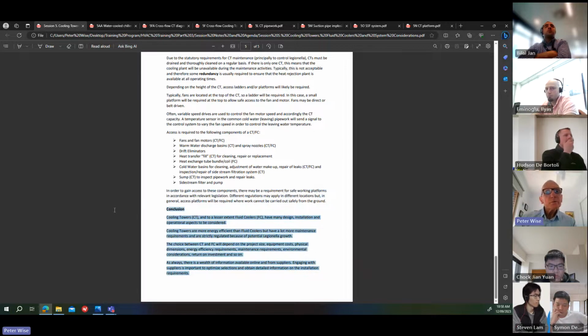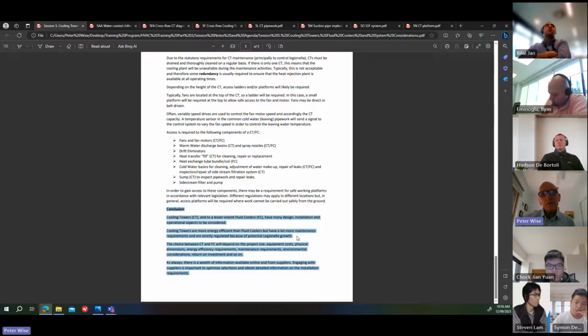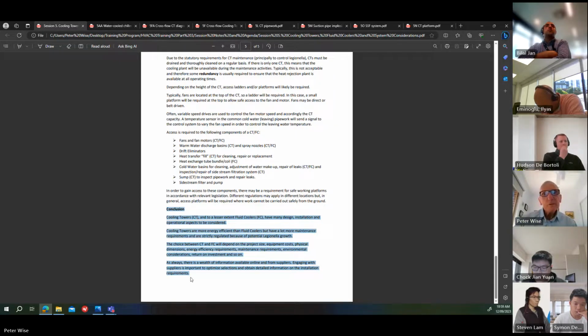So there's a fair bit to absorb there, but I just wanted to give you some awareness of what's involved and things to think about when you're selecting cooling towers. So cooling towers and to a lesser extent fluid coolers have many design, installation and operational aspects to be considered. Cooling towers are more energy efficient than fluid coolers, but have a lot more maintenance requirements and are strictly regulated because of potential Legionella growth. The choice between a cooling tower and fluid cooler will depend on the project size, equipment costs, physical dimensions, energy efficiency requirements, maintenance requirements, environmental considerations, return on investment, to name a few. Quite a few things to think about.